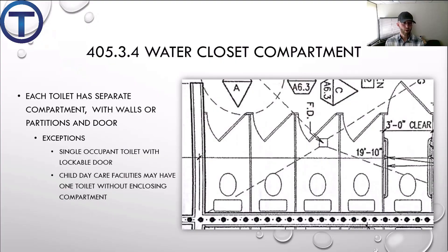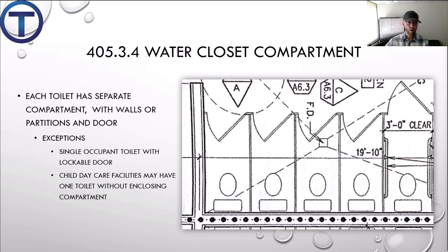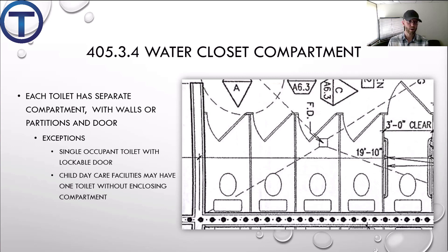405.3.4 water closet compartments requires that each toilet have a separate compartment, especially in a restroom with multiple toilets. Those toilets have to be separated by walls or partitions that have a door to ensure privacy. Exceptions: a single occupant toilet with a lockable door needs no partitions required. Daycare facilities may have one toilet that is not enclosed to help children who are potty training.